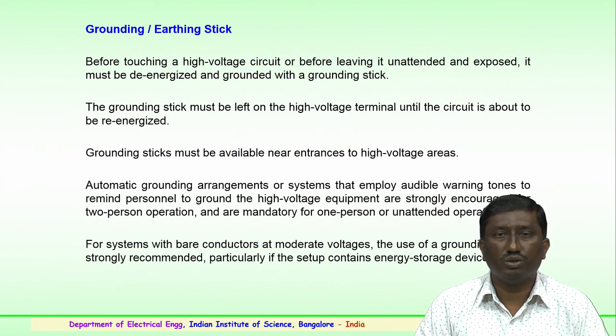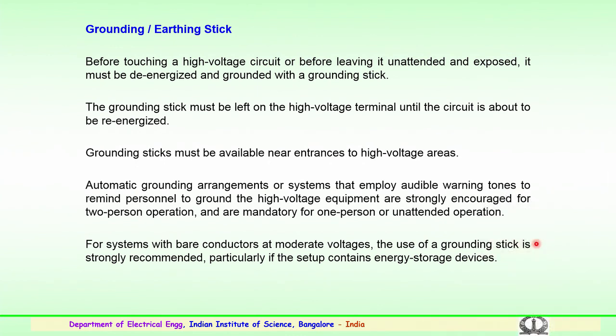So, during maintenance, the ground stick has to be connected continuously and the work has to be carried out. The grounding sticks must be available at the entrances of high voltage areas, and automatic grounding arrangements or systems with necessary audible warning tones to remind personnel to ground the high voltage equipment are strongly encouraged for 2-person operation and are mandatory for unattended operation. So, very important. For systems particularly with bare conductors at moderate voltages, the use of a ground stick is strongly recommended, particularly if the setup contains energy storage devices like capacitors or other devices.